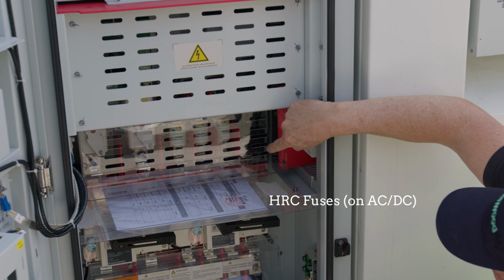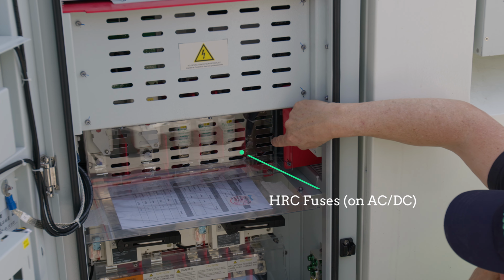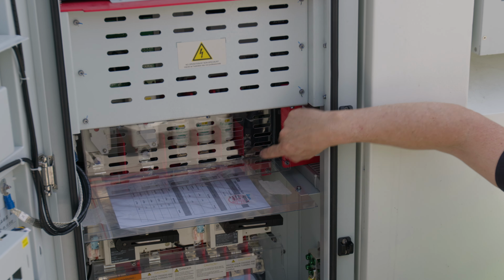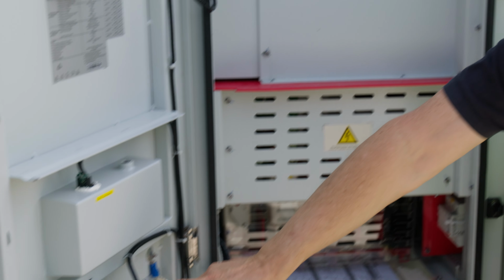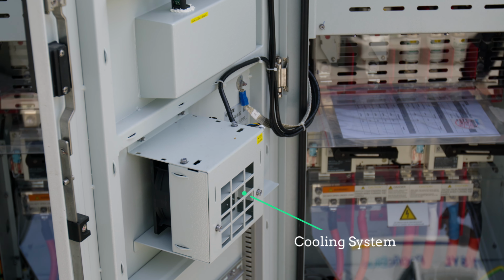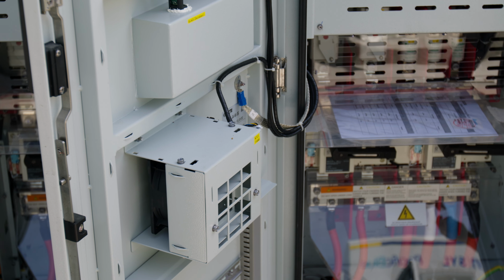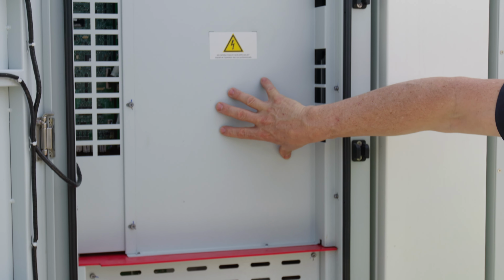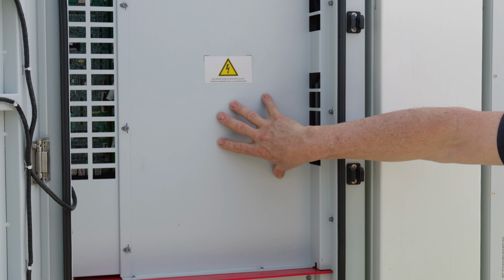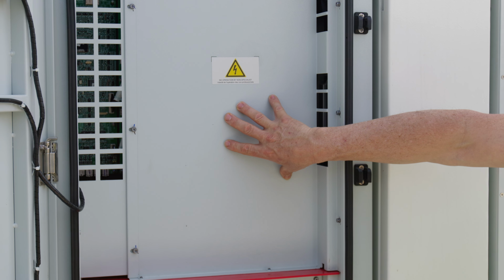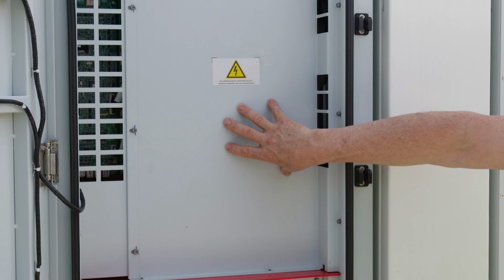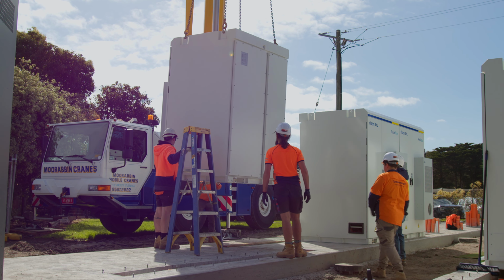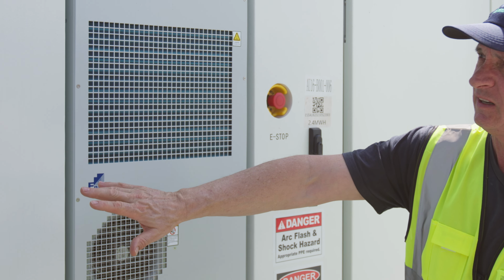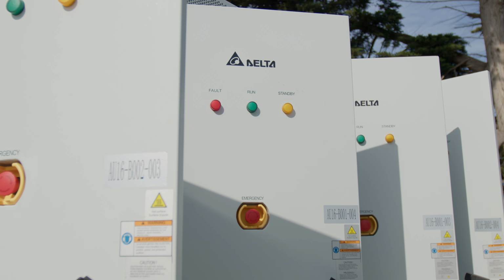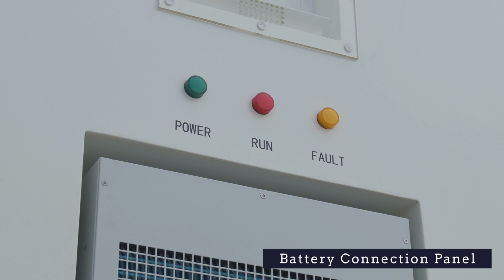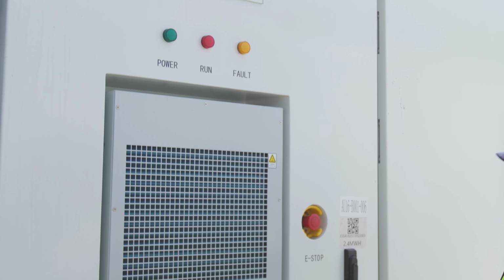Are they the HRC fuses? Yes, there's HRC fuses on the AC and DC connections. Right, to protect both the installation and the cabling. So these particular inverters have, as Alex has pointed out, forced air cooling, but they don't have an HVAC system like the batteries do. Now, obviously, this is the inverter here behind this. Which makes them rather top heavy. The inverter is mounted in the top section of the unit, which is good for heat on the actual control gear, so it keeps the control gear nice and cool. But it does make them top heavy when you're moving them around. And then right next to this particular bank of inverters is one of the battery cabinets. That one there is a battery connection panel, which is basically control gear for all of the batteries and the inverters.